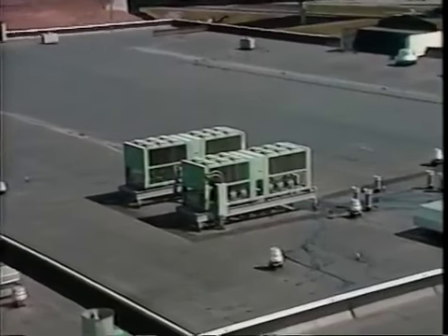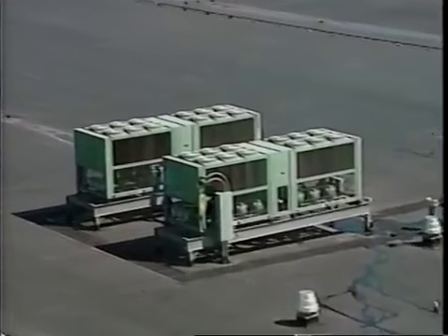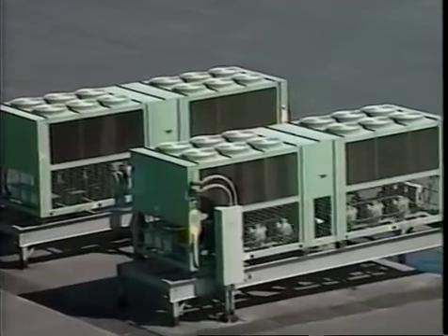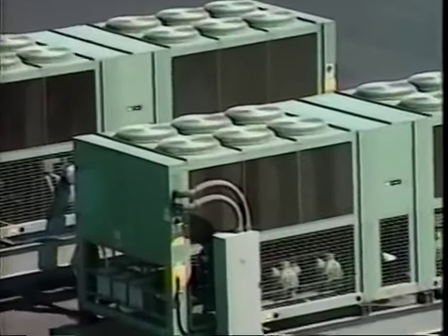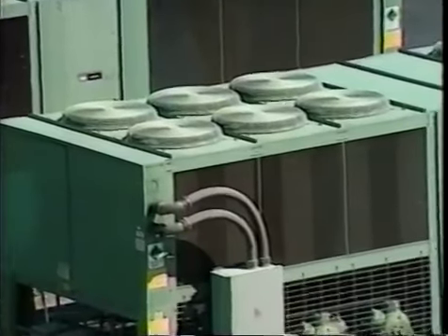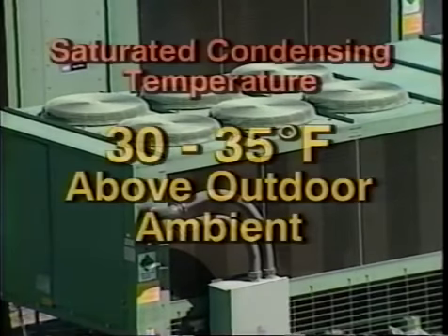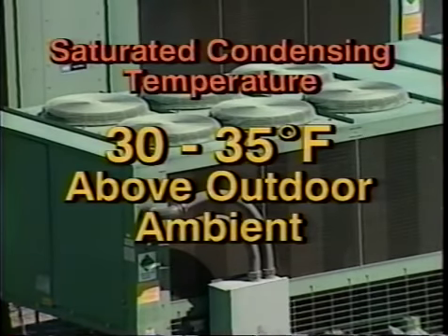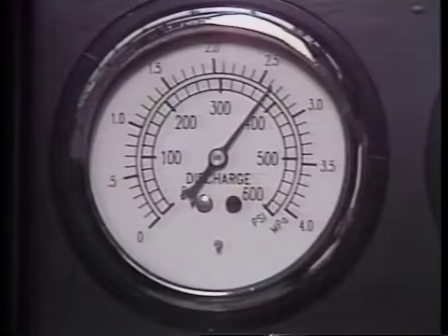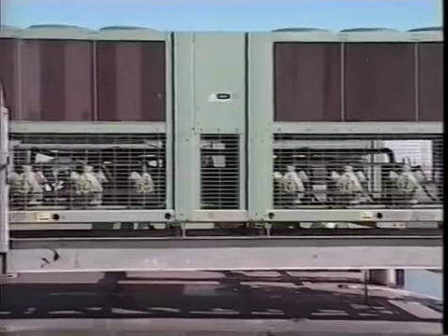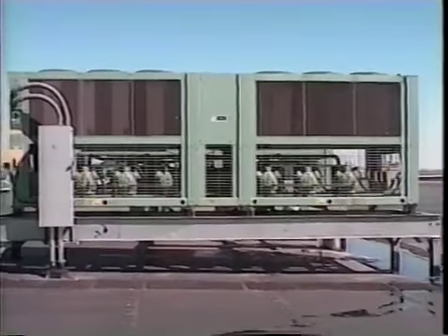Many chillers use air-cooled condensers with propeller fans drawing ambient air over the condenser coils. If an air-cooled condenser is used, the saturated condensing temperature at full load will typically be about 30 to 35 degrees Fahrenheit above the outdoor ambient. An increase in the condensing pressure may be an indication that the condensing coil is getting dirty. Cleaning the condensing coil from time to time, at least once a year, or more often if required, will assure optimum efficiency.